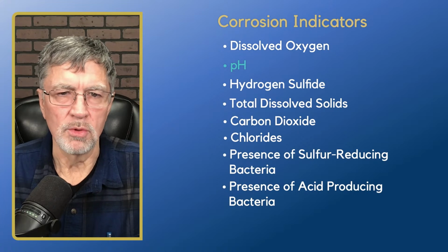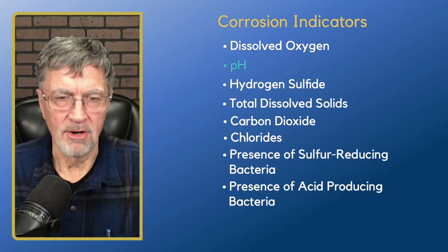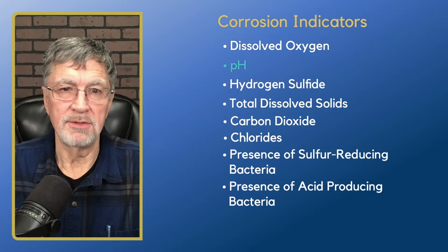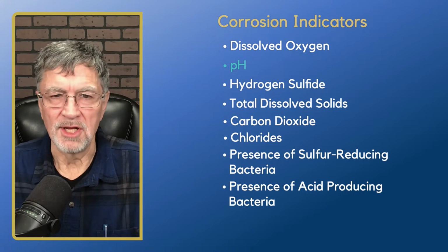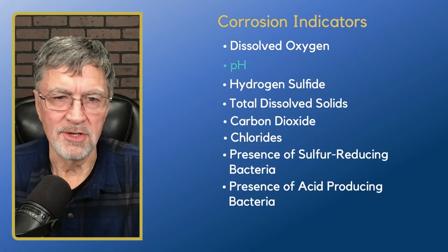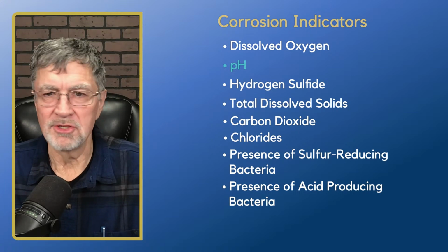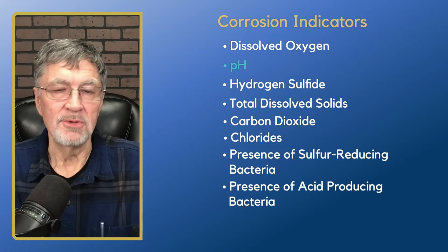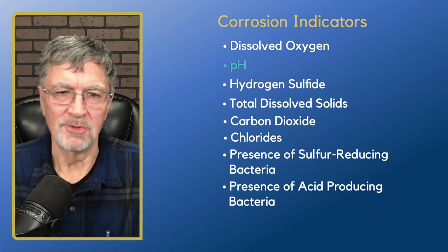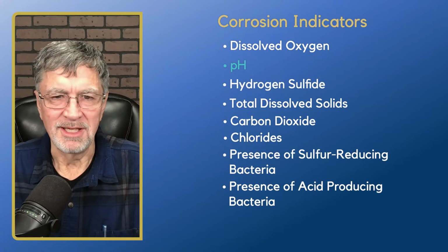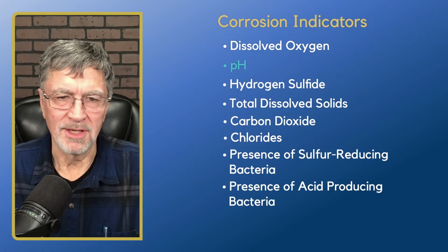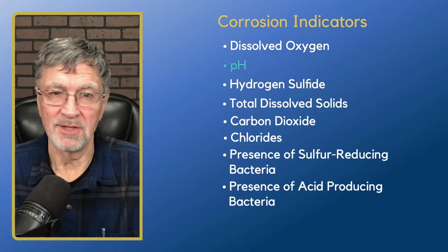And the more acidic your well, the more likely you are to have corrosion going on to your metal. And you can even corrode stainless steel. It takes a lot longer to do, but in conjunction with other things like chlorides, you can actually corrode stainless steel. So it's a myth that it does not corrode. It will corrode, and more acidic solutions can definitely damage stainless steel.